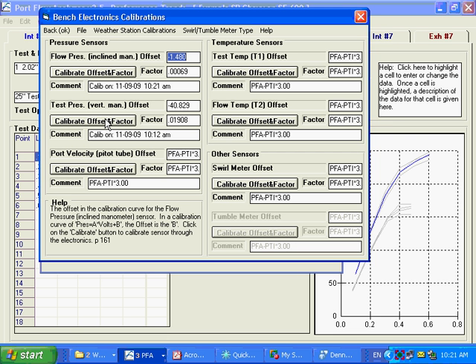This time, instead of setting 70 to 90% of full scale, I would suggest trying to set for the upscale exactly what you're, within a couple tenths or a half inch of what you flow at. If it's 10 inches, try and set something around 10 inches. If you flow at 28, set something around 28. Because what else happens in the rest of the scale is not really important at all, because you're going to be setting 25 or 28 all the time.